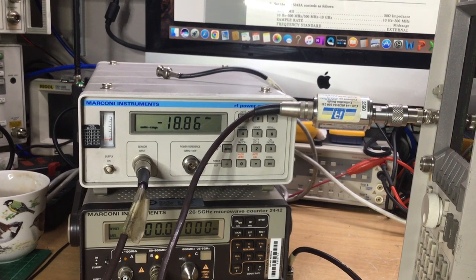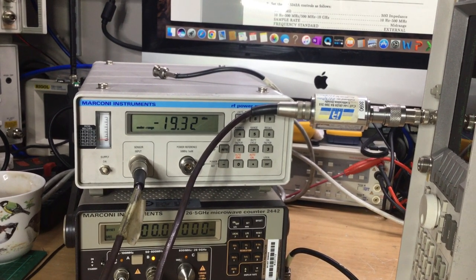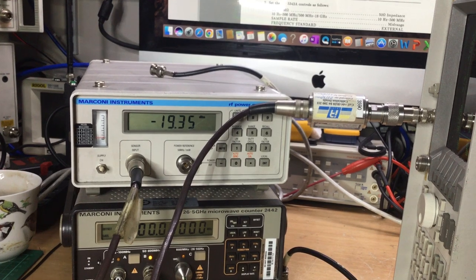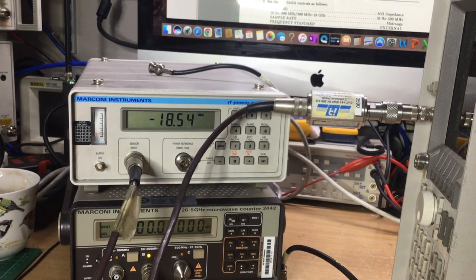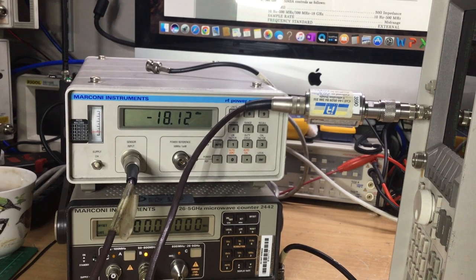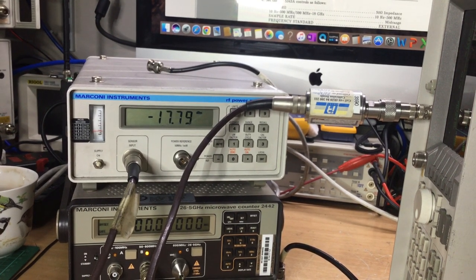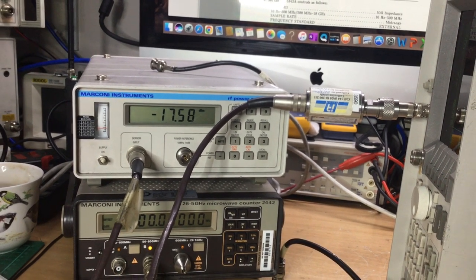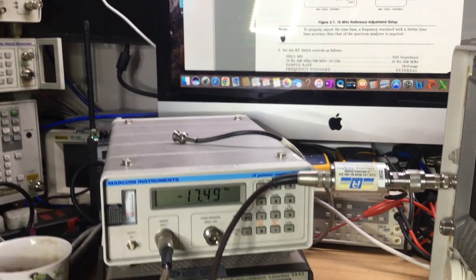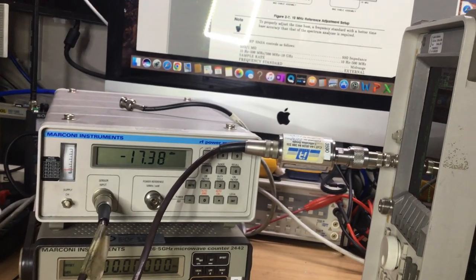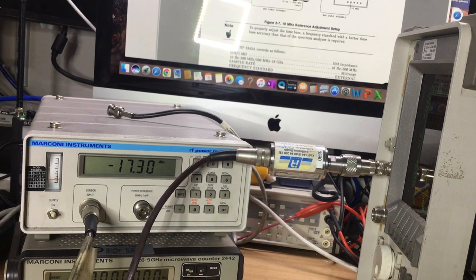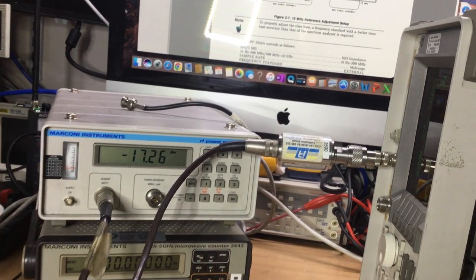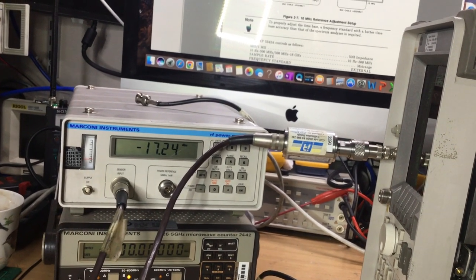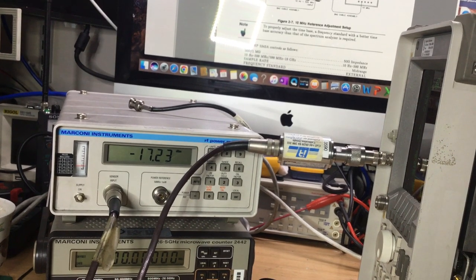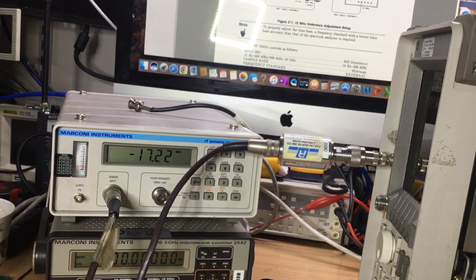Well, that's getting worse when I turn it. Now it's gone under range, obviously, because it's gone above minus 19 dBm. Let's see whether it gets down to minus 10. So I'm just turning it clockwise. Now it's fully clockwise, and it will only go down at fully clockwise to minus 17 dBm, which is not ideal, obviously. It needs to be minus 10, and I can't get any more adjustment out of it. So obviously that's an issue.